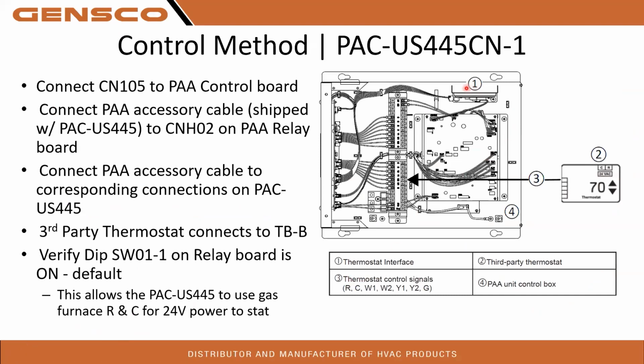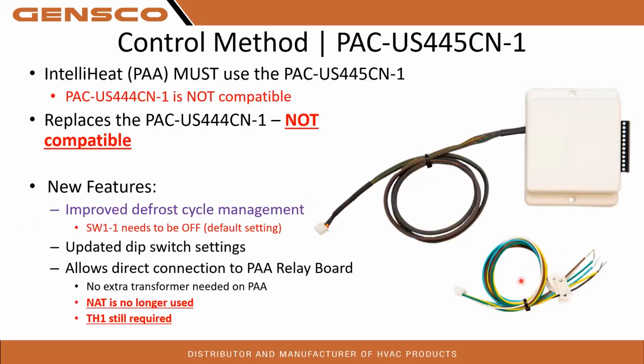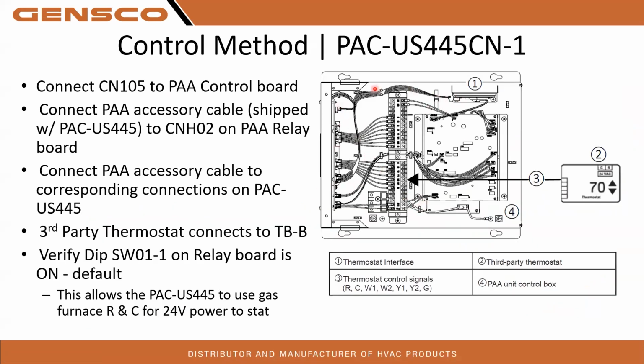So this is the control board. This is our PAC 445 up here. One thing to note is, if you guys have used these 24-volt interfaces before, these are a little bit different. Your thermostat does not wire into the 445 on the Intelli-Heat coil setup. It comes with a pigtail, which is this little pigtail right here. This is what wires into the 445 right here. This pigtail is going to wire into your control board or the relay board down below here. See that right here? It comes down and wires into that. Your thermostat is going to wire onto the TBB terminal blocks, and then from there, it goes down to the relay board. That way the system can control everything, and then it communicates back to the 445.